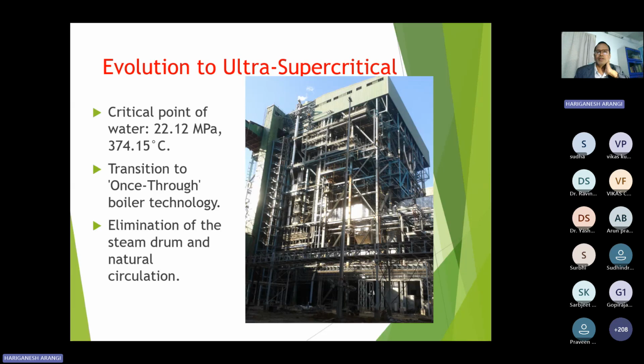Another improvement process is using ultra supercritical boilers. These are high pressure boilers where water gets directly converted into steam. There will not be any steam drum or steam separation. It is called once-through boiler technology.